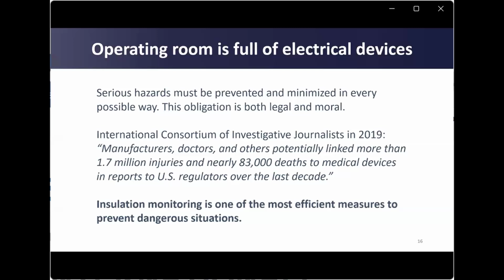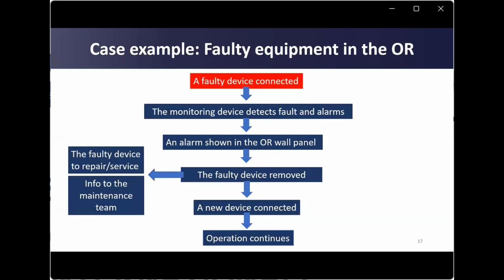Insulation monitoring is one of the most efficient measures to prevent dangerous situations. Here is a case example of how operating room staff should act when faulty equipment is detected in the operating room. A faulty device is connected or detected. The monitoring device detects the fault and alarms. An alarm is shown on the OR wall panel. The faulty device is removed and sent to repair, and information is sent to the maintenance team. A new device is connected and the operation continues.